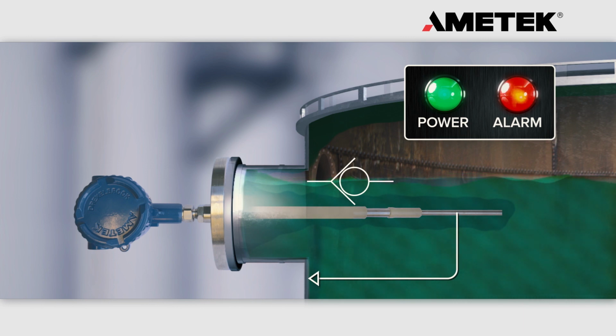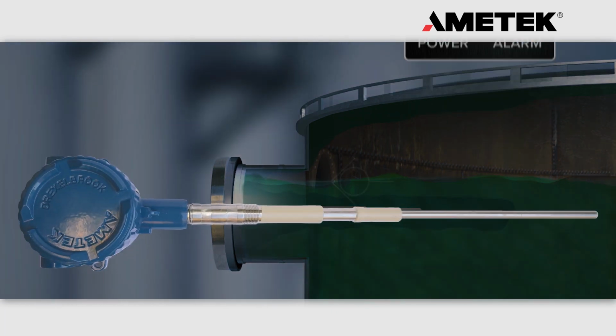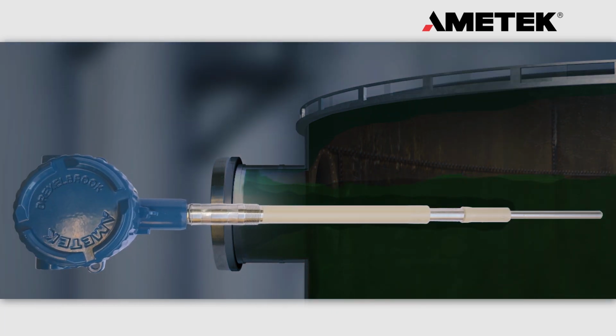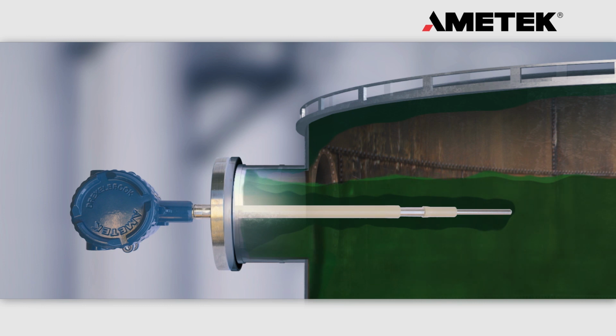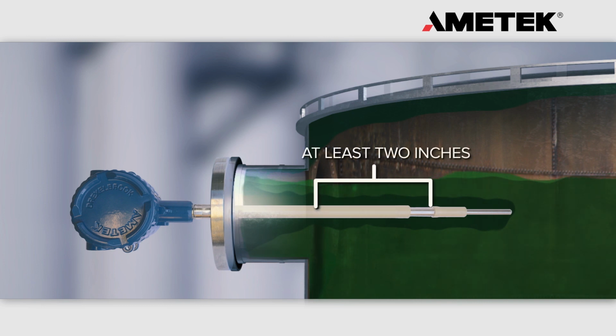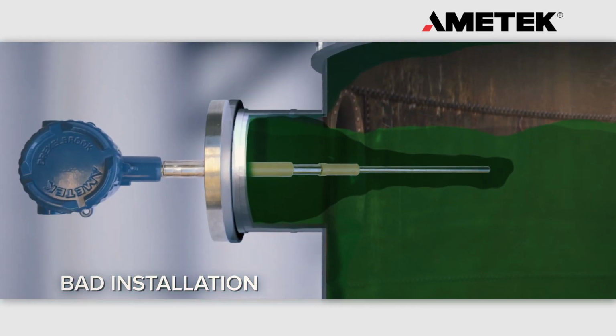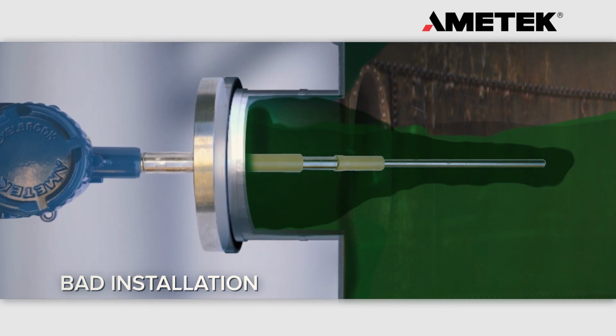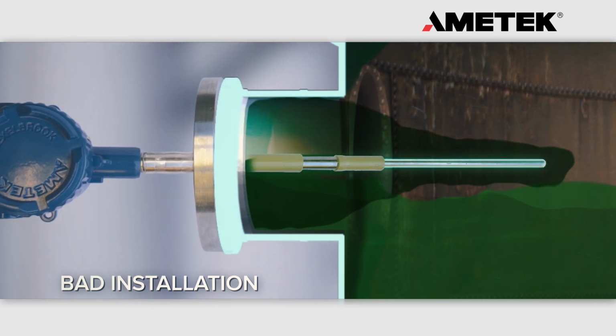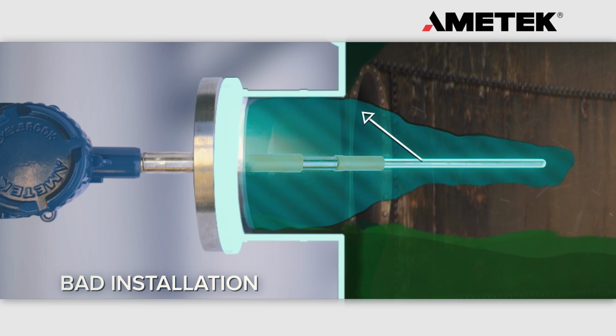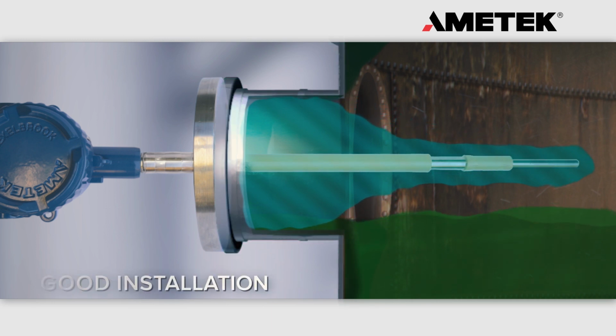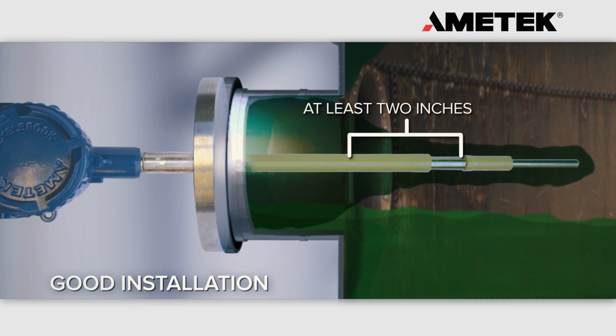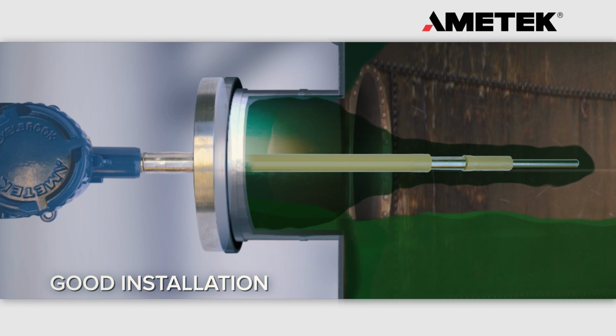For Cote-Shield to work effectively in your application, we have one very important rule. The Cote-Shield needs to extend into the tank past your installation nozzle and any wall buildup by at least 2 inches. Let's see an example of what happens when this rule isn't met. When Cote-Shield is buried inside the nozzle, we are essentially bringing ground closer to the active rod than Cote-Shield. This creates a more effective path to ground and bypasses Cote-Shield. This is why it's important to have the Cote-Shield portion of the probe extend past the wall and any wall buildup. This places Cote-Shield in the direct path between the active rod and ground.